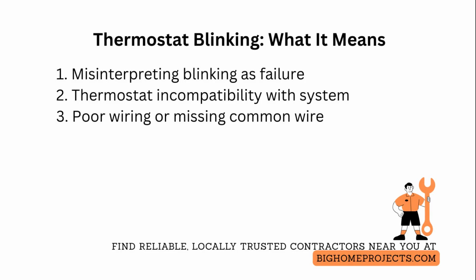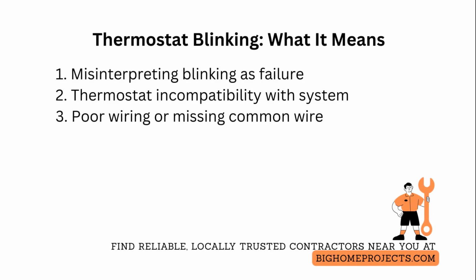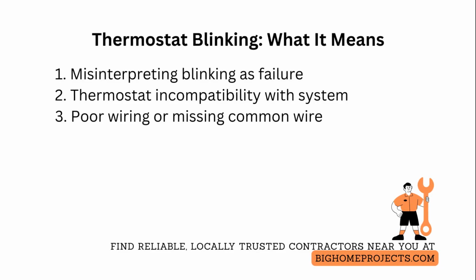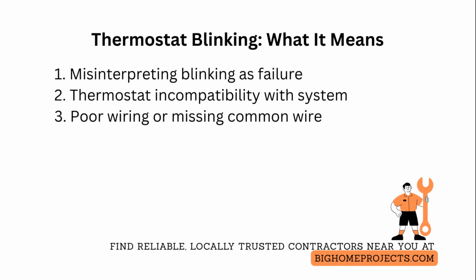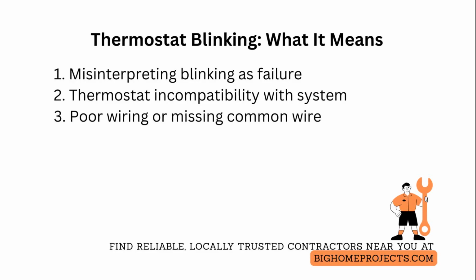Another common issue is replacing the thermostat with a unit that does not respect compressor protection delays or is incompatible with heat pump and inverter systems. Remedy that by selecting a thermostat listed compatible with your system type and configuring minimum cycle protection and equipment type in the installer setup.